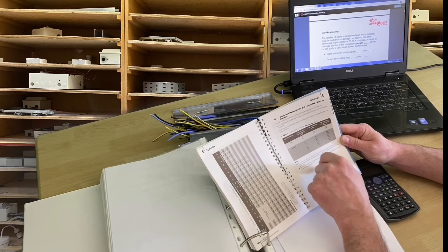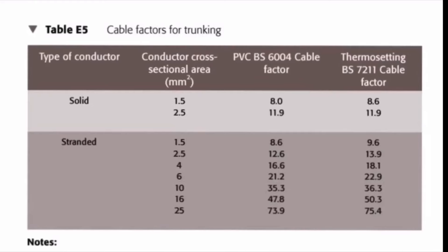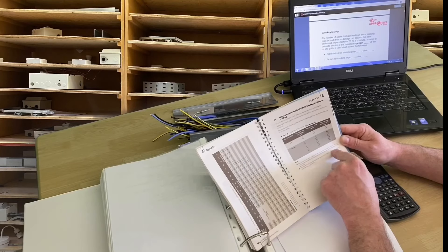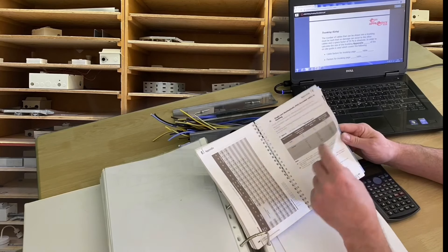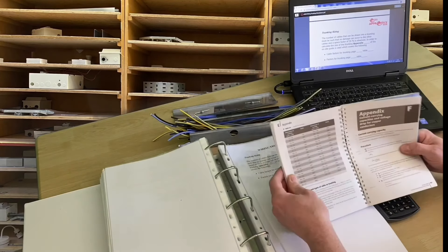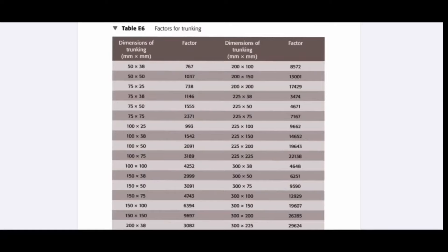For these notes I'm going to be concentrating on the stranded section and on the thermoplastic PVC — BS6004 cables. That's where we get the factor for the cables themselves, exactly the same as we did in conduit. We then turn over to the next table, which is table E6 — the factors for trunking.